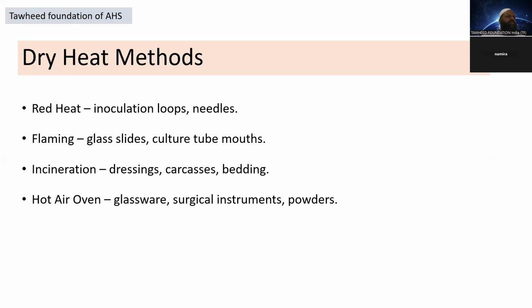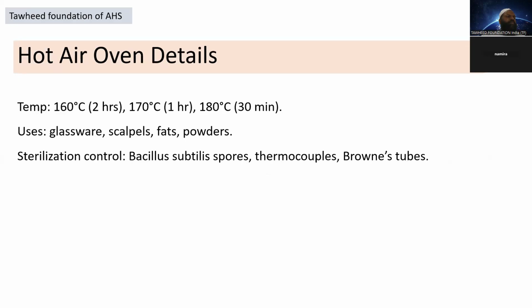Hot air oven. It is a widely used method of sterilization by dry heat. The heat inside the oven is maintained by electricity and a fan fitted inside. It provides adequate distribution of hot air inside the chamber. A thermostat is also connected, which maintains the temperature inside the chamber. 160 degrees Celsius for 2 hours is required for sterilization.